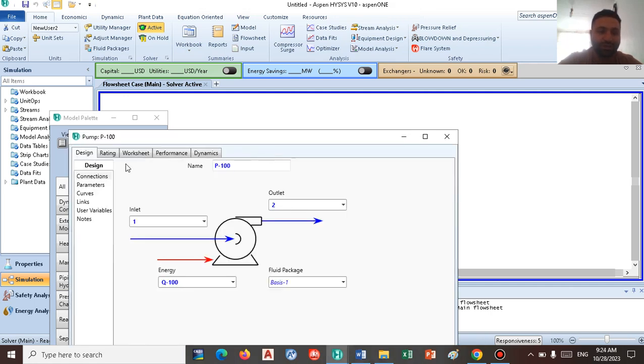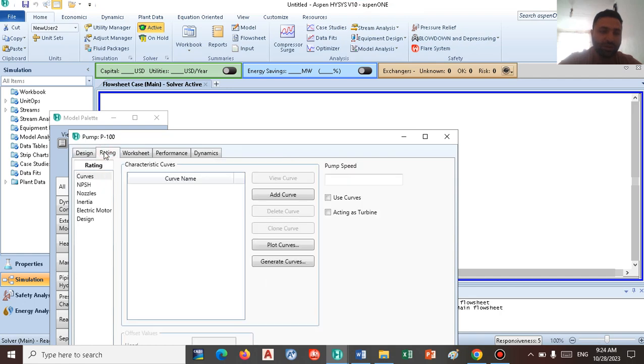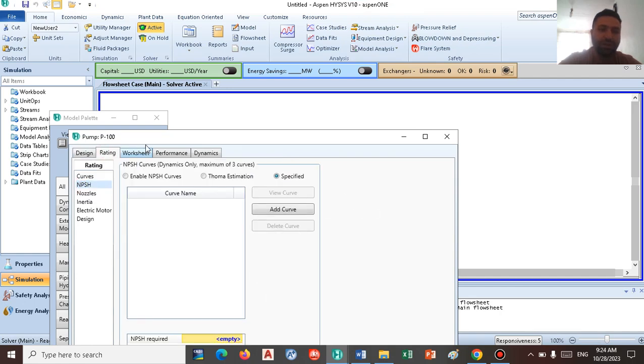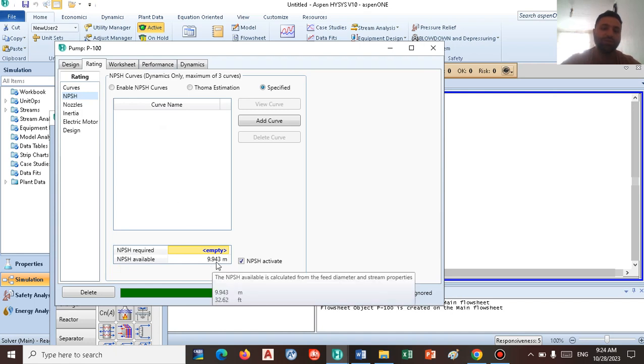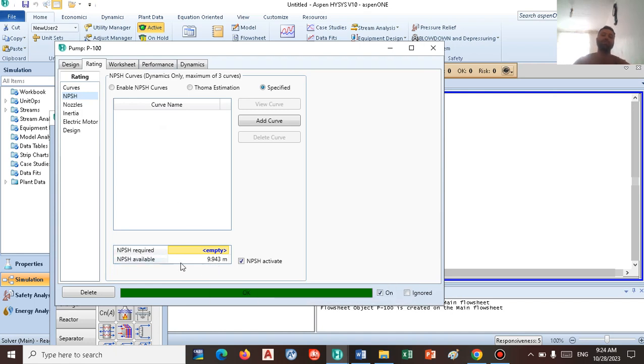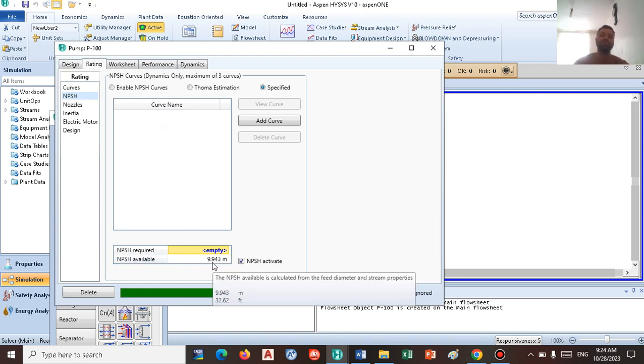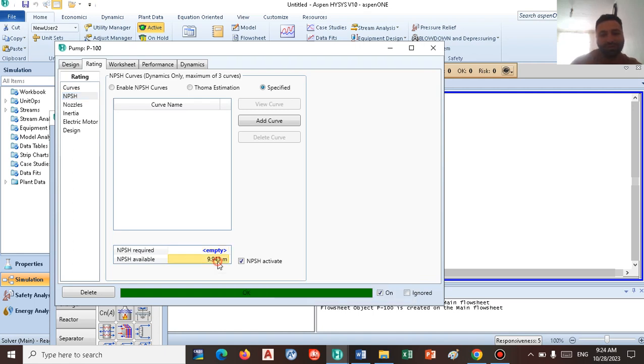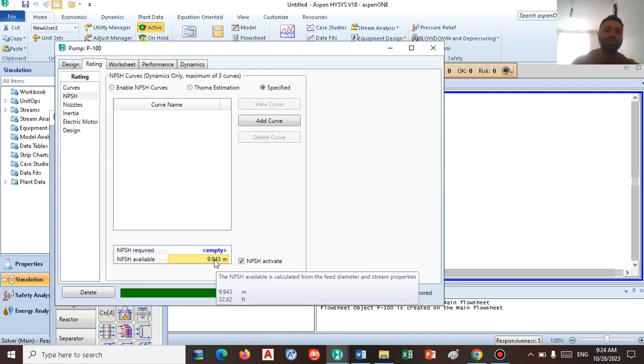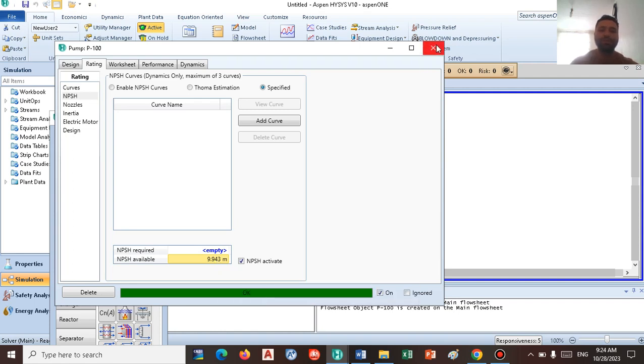So HySys automatically goes to the rating tab and automatically calculates NPSH for us. This is right here. NPSH available is 9.9. So how does HySys work and how does it calculate this number? I'm going to show you how to calculate this number by yourself.